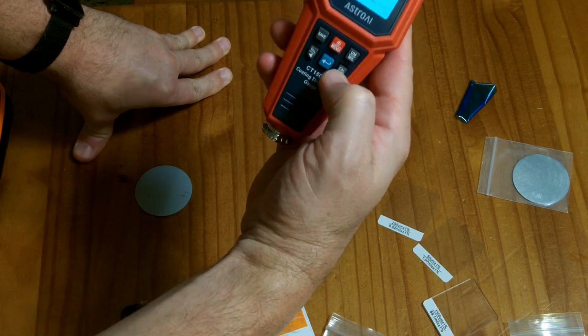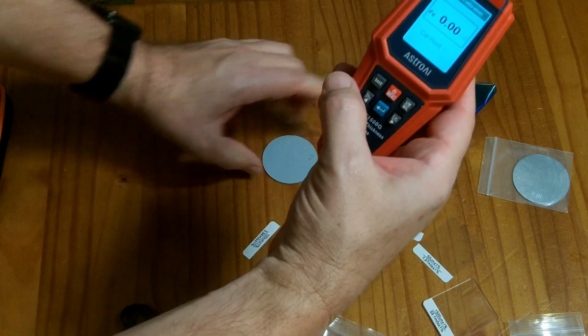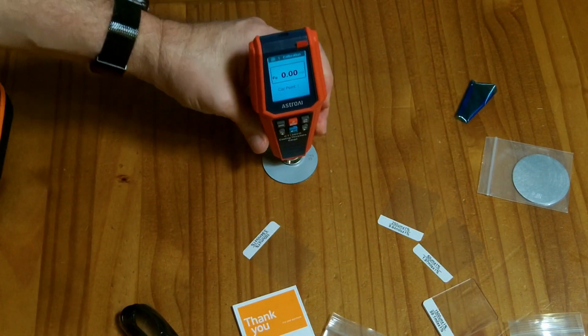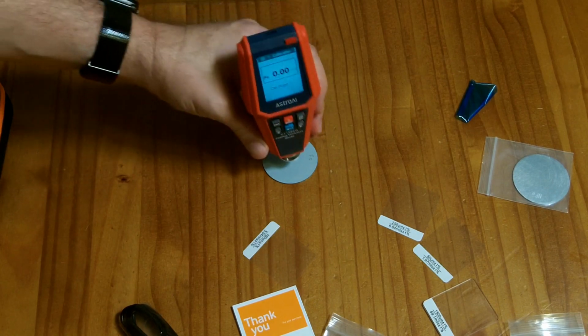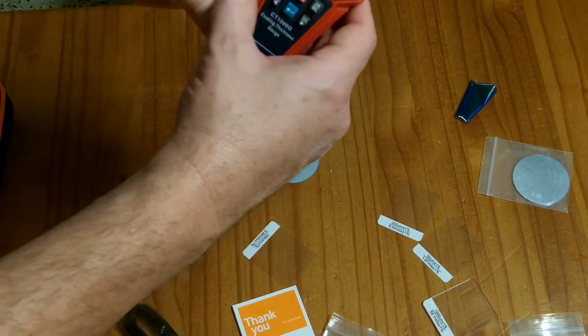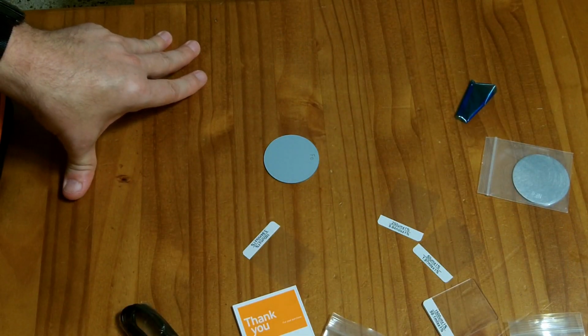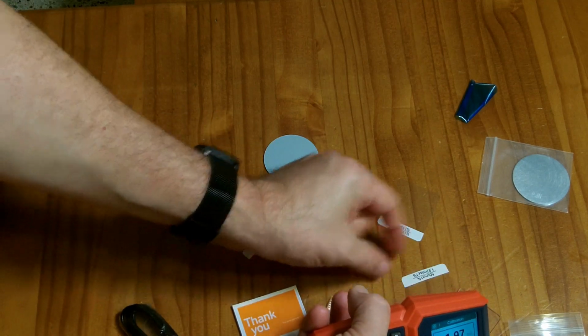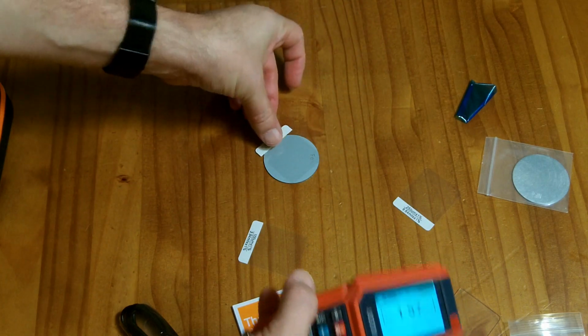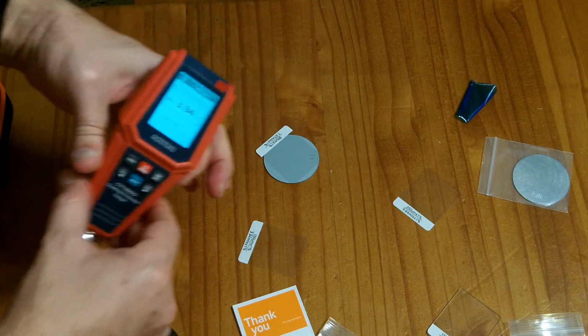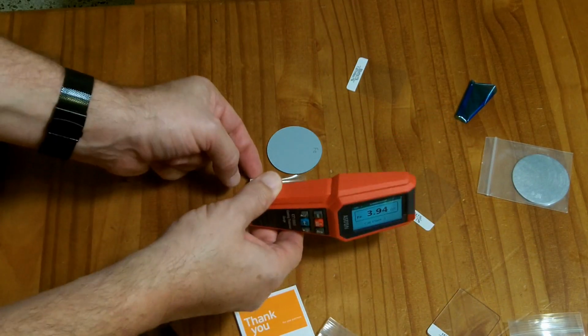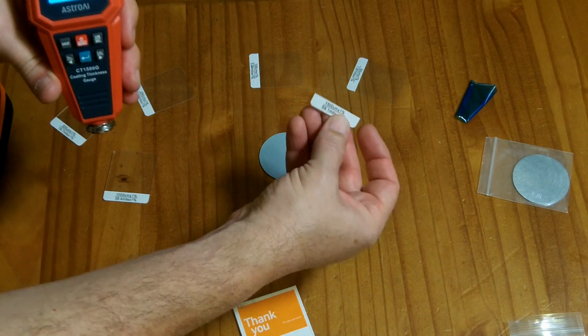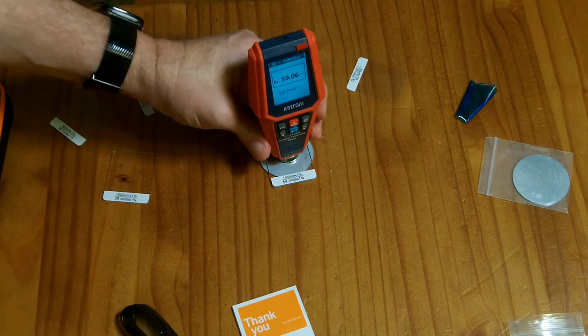They have a calibration thing here. So it says calibration 1, FE, ferrous, 0. So there it did that. And now it wants calibration 0.2, which is 1.9 mils. And so that is 1.97 mils is 50 micrometers. And now it's jumping up to the 3.94 mils. And now it wants the 59.06, in this case 59.1. All right, so it is now calibrated.